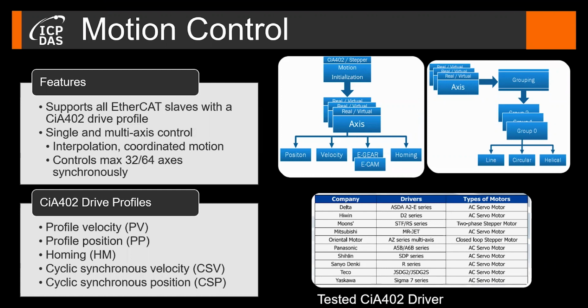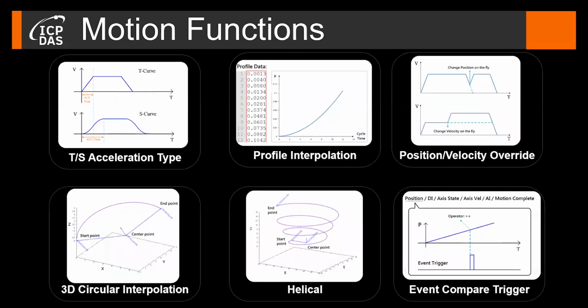The table below lists the servo drives that have been successfully tested together with our EtherCAT-based motion engine. All CiA 402 drive profiles are supported. Virtual axis functionality is available, which means a servo or stepper drive does not need to be online for the motion engine to generate a motion path. Most single and multi-axis motion commands are implemented according to the PLCopen-defined specification. This slide shows some basic motion control features supported by our controller, such as T and S curve acceleration, contouring, movement, change velocity on the fly and position on the fly, multi-axis, linear, circular, and helical movement, etc.